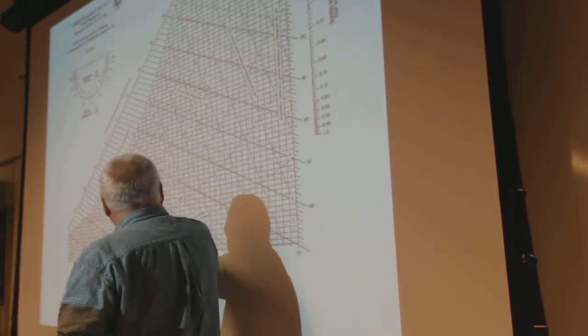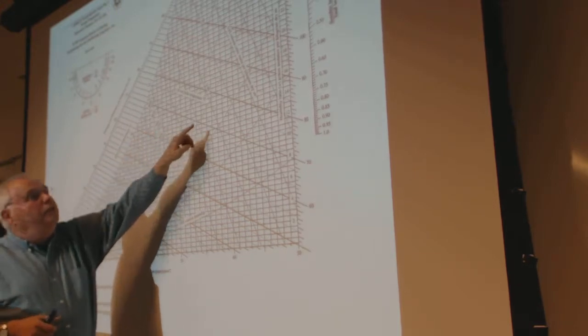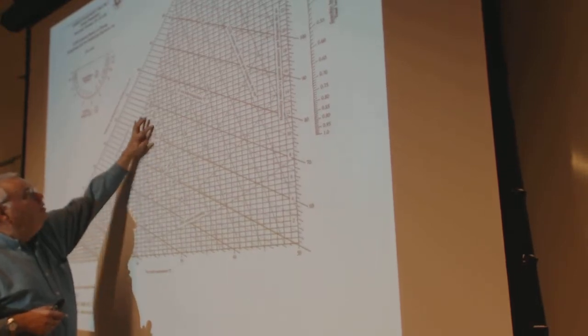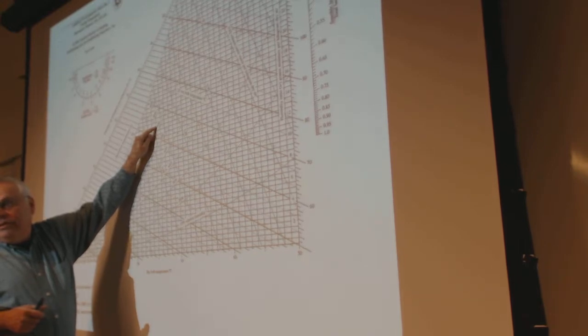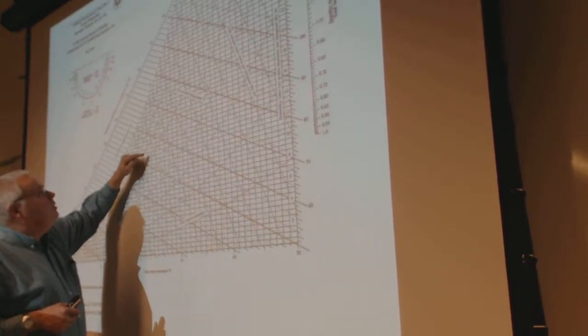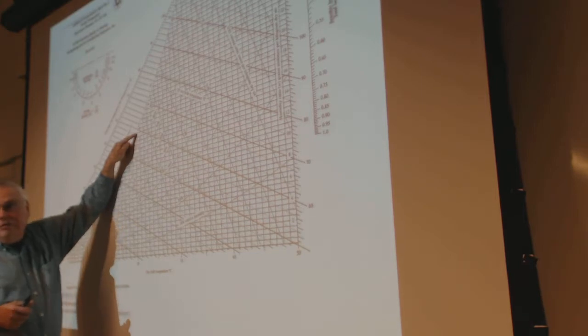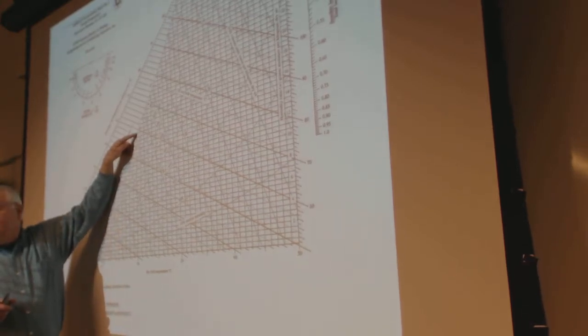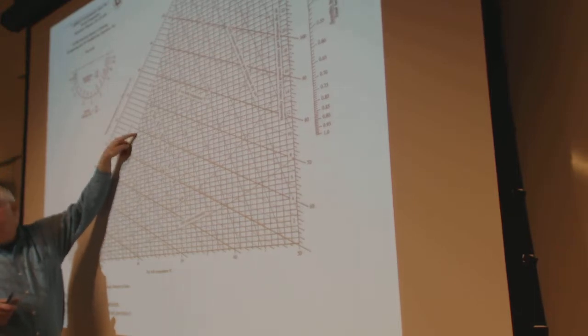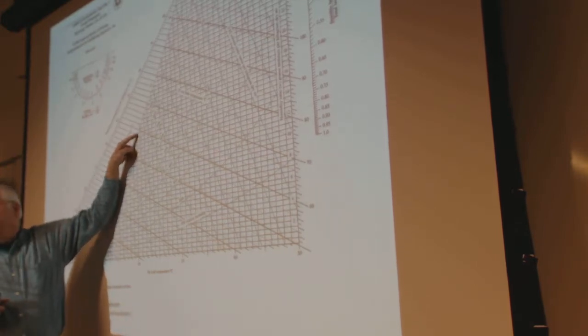So, at this point where we were, the dew point on it would be, if you drive the moisture at 15 grams per kilogram, and you cool it down until it hits this curve, you're going to have the same value. This doesn't change. It's staying the same, but you can cool it off. If I just cool it down, it'll keep cooling down until it hits the curve, and that's going to be my dew point. Because now it's 100% relative humidity. If I cool it anymore, we have to lose moisture, and that means phase change, that's the stuff that's condensing on your glass. So, in this case, at 20 degrees C, things are going to start condensing.